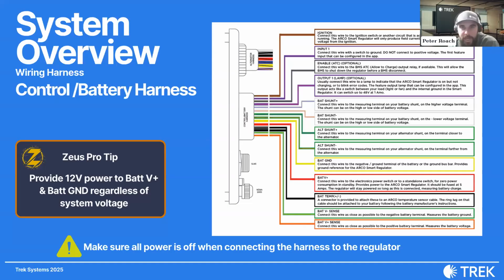Then moving down to the battery shunt connections - there are two shunts in this system. There's one on the positive output of the alternator that shows us what the alternator is outputting, and then there's a battery shunt in your battery system. For systems that do not have a Cerbo GX, you will connect these battery shunt cables to the shunt that's in the system.